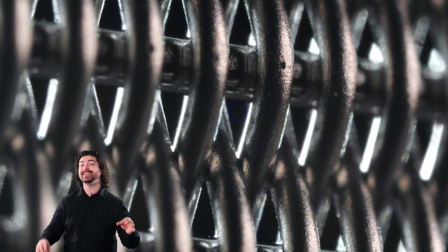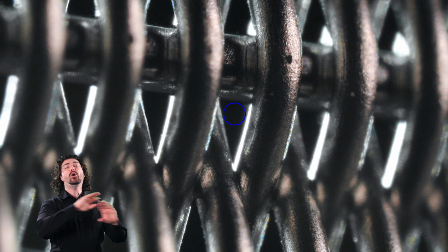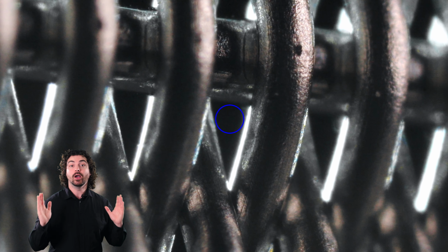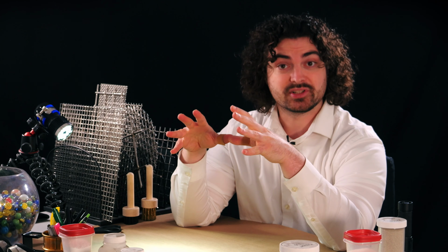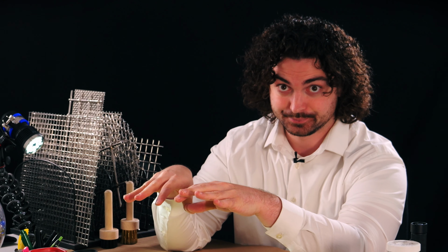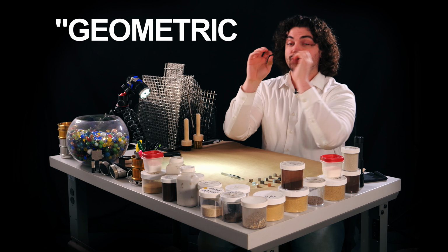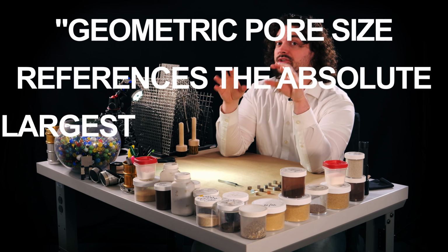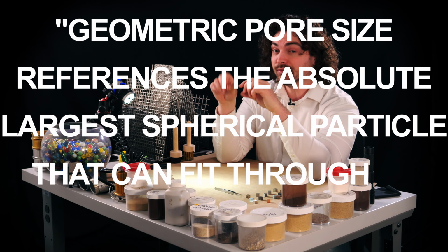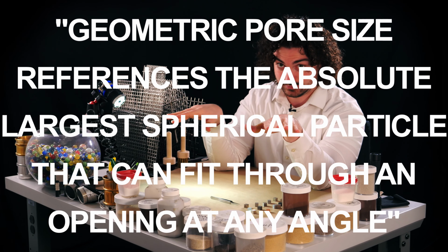This crazy important spec is called geometric pore size, and it's the whole reason that woven wire mesh does what it does. And oddly enough, this measurement is a scientific way to fit a circular peg through a square hole. Don't think about that sentence too much, it's exactly how it goes. It's time for the definition. Geometric pore size references the absolute largest spherical particle that can fit through an opening at any angle. Let me repeat that. Geometric pore size references the absolute largest spherical particle that can fit through an opening at any angle.